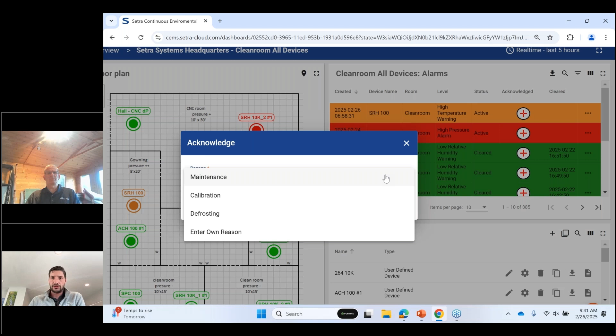This is part of that 21 CFR Part 11 compliance, where essentially it'll capture the full trail of the alarms of when it was triggered, who acknowledged it, as well as what was done to get the alarm back into the acceptable levels. So let me show you that.